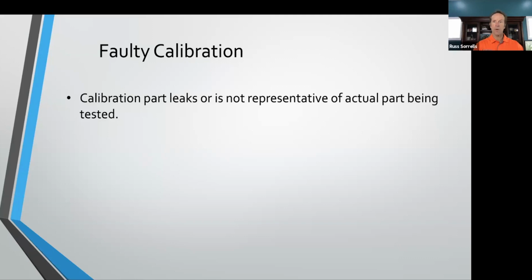Absolutely, that's a great point. That is a great way to do some testing and check to make sure you have a good calibration: use a leak standard that's 10% over your reject limit and 10% under your reject limit. One should give you a red light, and the other should give you a green light.